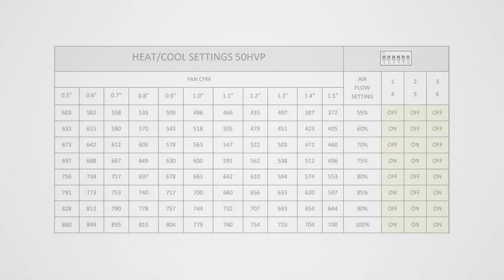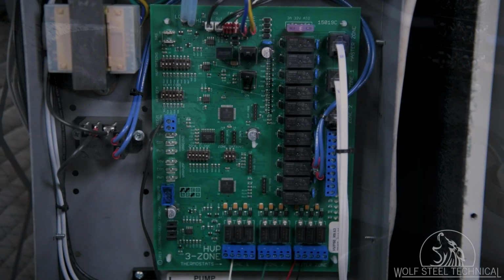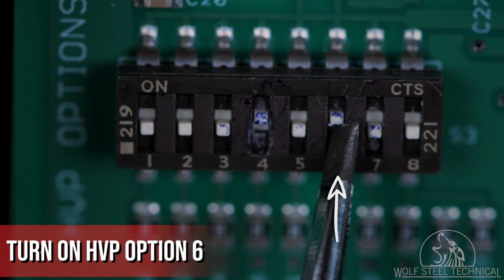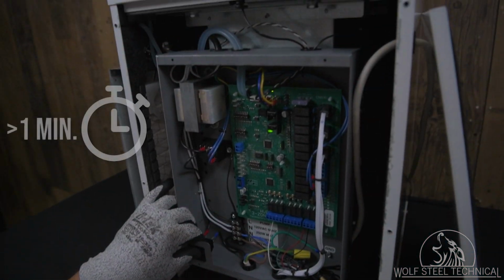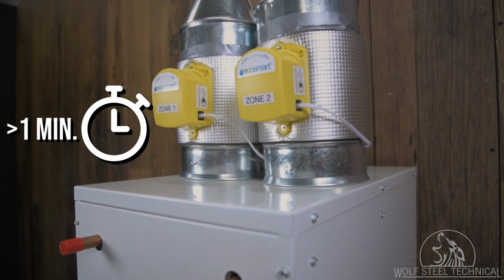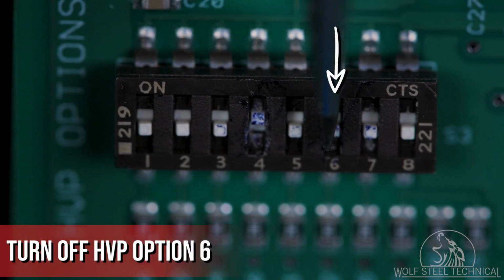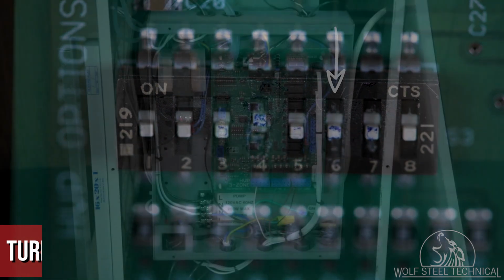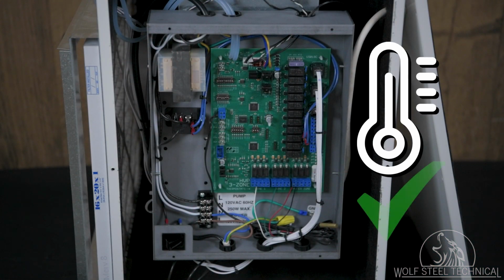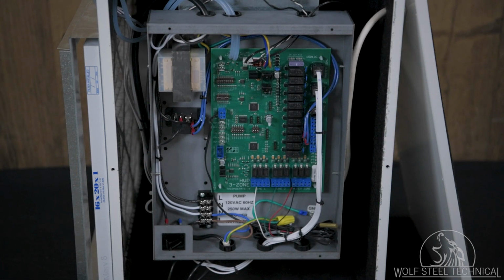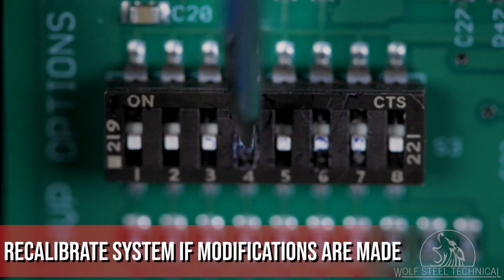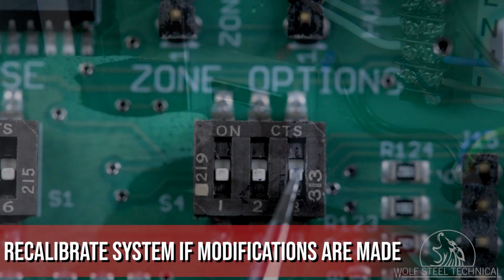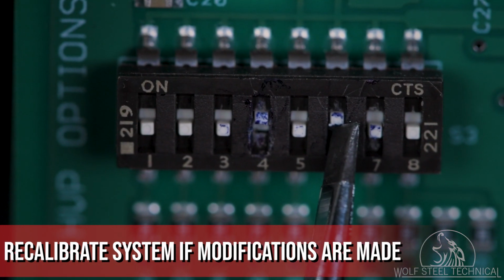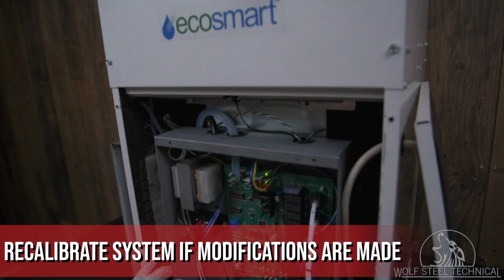the installation. Keep holding the door switch and set the HVP option 6 switch to on, allowing the system to run for at least 1 minute. Once 1 or more minutes have passed, set HVP option 6 to the off position. The heating calibration parameter is now permanently stored in the controller and will be retained even in the case of a power loss. If for any reason modifications are made to the system, such as adding or reducing ducting, the calibration must be repeated to ensure correct operation.